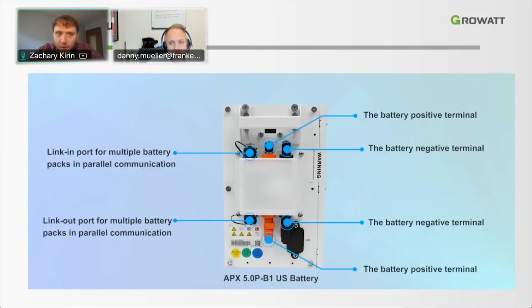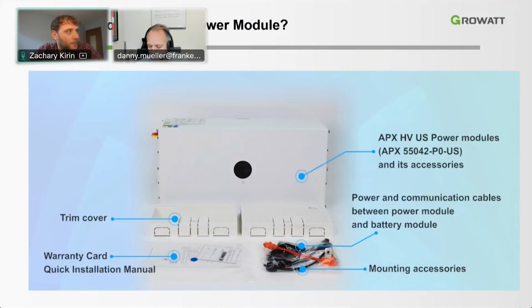Moving on to the battery module interface. We have the link in ports and the link out ports for the battery communication. The way everything is designed is daisy chain technology. The in ports for the battery positive terminal from the battery above will be input here, and then the next battery in the stack will be input here at the output. So the battery can be installed floor to ceiling, or you can separate the battery clusters into sections of 3, sections of 4 and 2, anything within 30 kilowatt hours. So we're giving you a little bit more expandability here as well. We'll detail that in the next couple of slides.